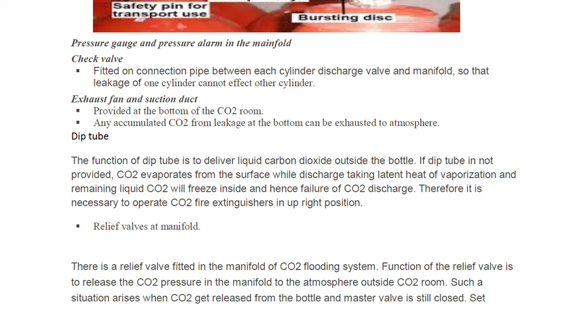Therefore it is necessary to operate a CO2 fire extinguisher in the upright position. Whether it is a portable one or fixed CO2 bottles, we have a dip tube in both cases — irrespective of the size of the CO2 fire extinguisher. We also have relief valves at the manifold. There is a relief valve fitted in the manifold of the CO2 flooding system, whose function is to release CO2 pressure.